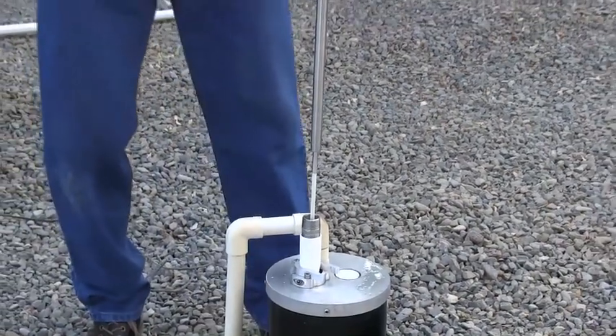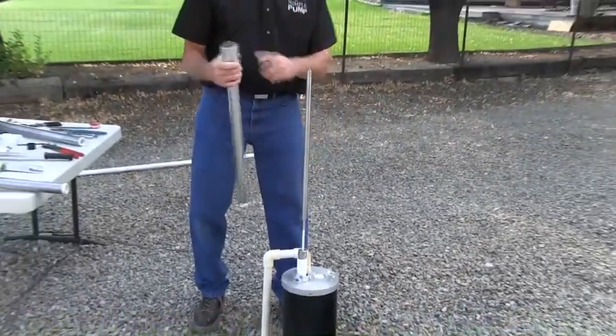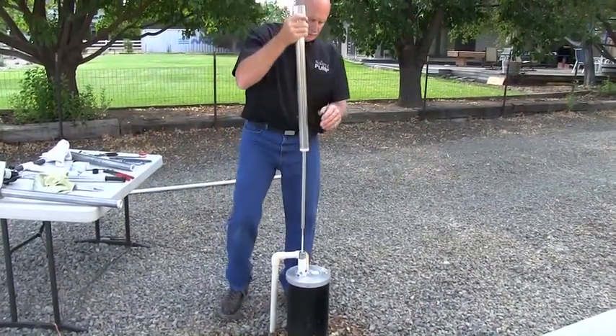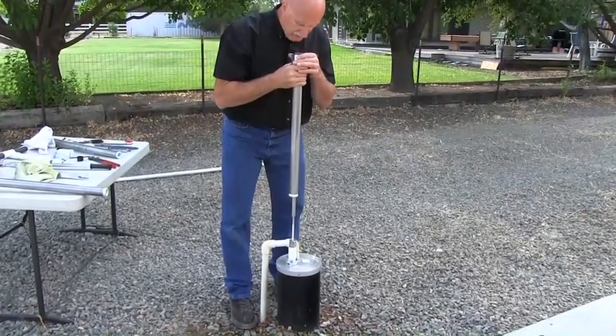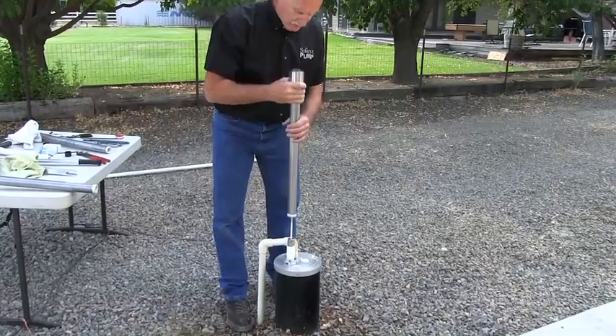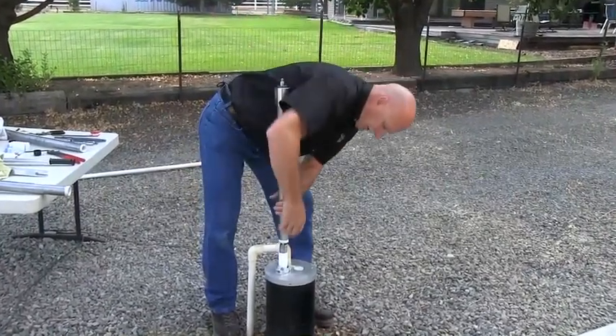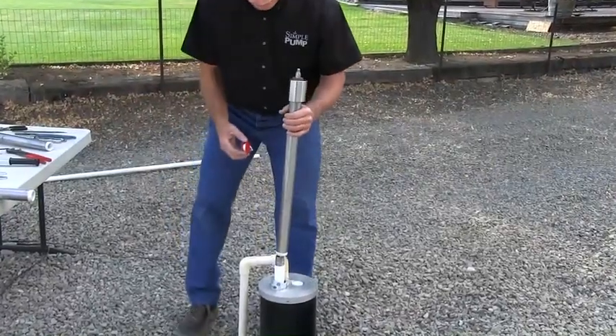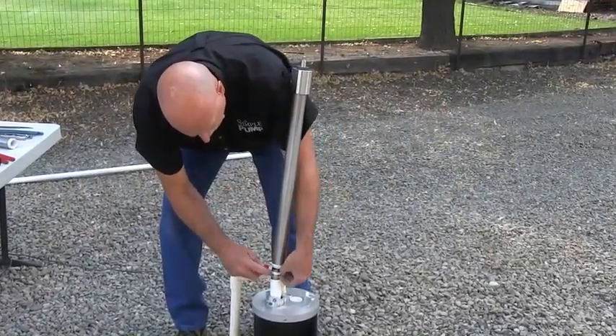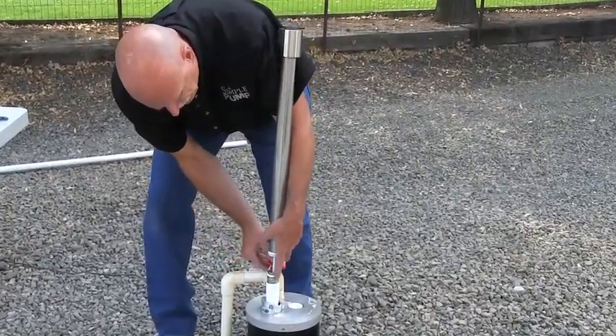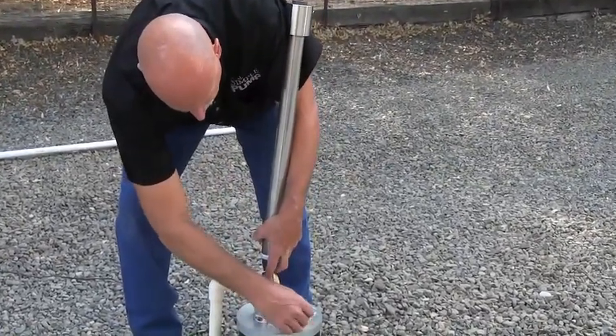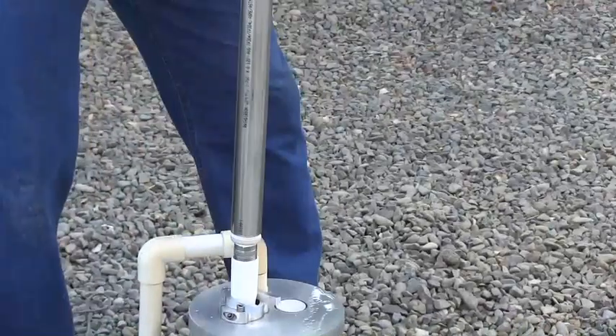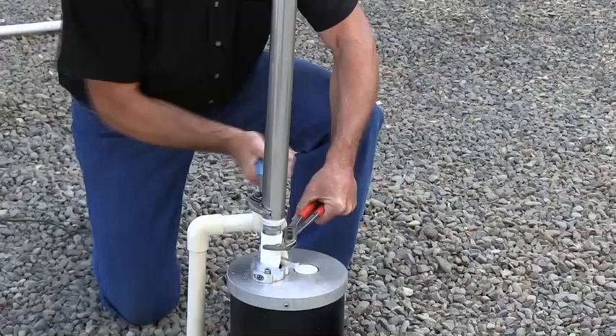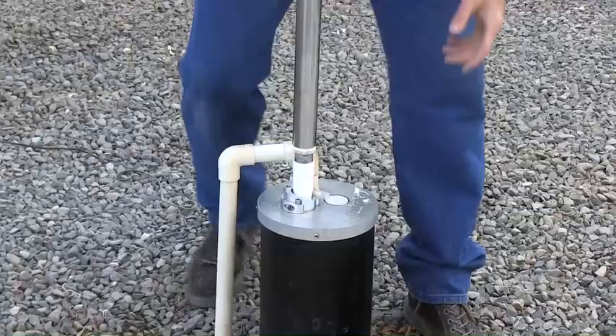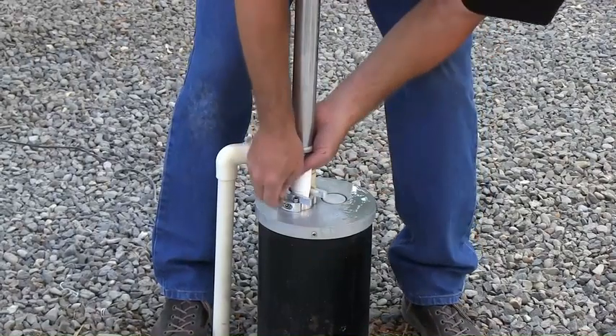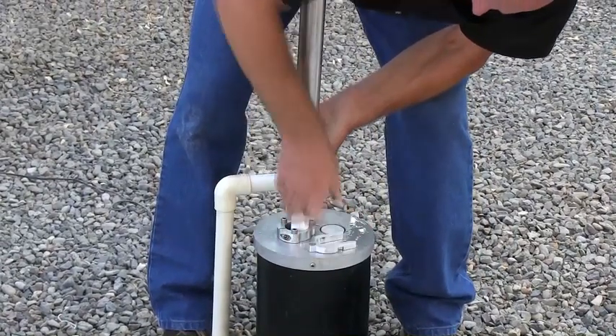Then the next piece that we're going to bring in is the riser tube and pump head. There's an 8-inch long rod gland inside of the pump head, so we want to align that stainless rod to relate to that. Again, some Teflon tape on these threads would probably be in order. Three wraps would be good enough. Now we are ready to remove the safety tool, lifting up a little bit on the bell end.